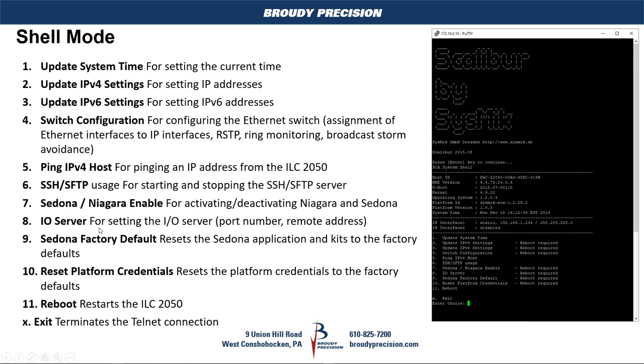Additional menu options include enabling SFTP to allow you to go in with an FTP client such as FileZilla to access the file space in the ILC 2050. You can change the IO server port settings, default restore the Sedona application, reset platform credentials — which we'll go through today — and also do a reboot or exit out of the telnet session.